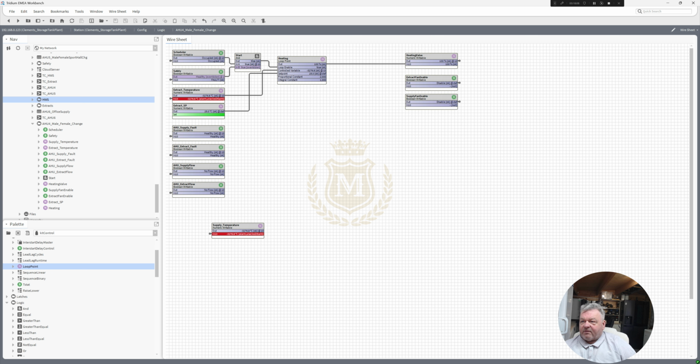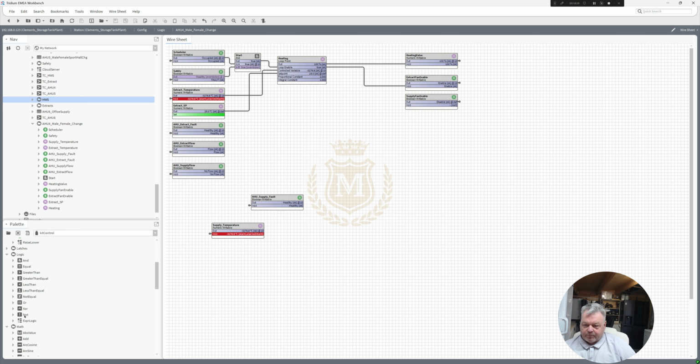So as we've got this here, I can go from here, or I can actually go from here. And I'm going to go there to run the extract fan. Now we have an extract fan fault here. And then we've got the extract fan flow here. So there's no point in enabling up that if we've actually got a fault here. So because I know that's going to be a false, I know it says healthy, but we'll put a NOT gate in there. Reverse extract.